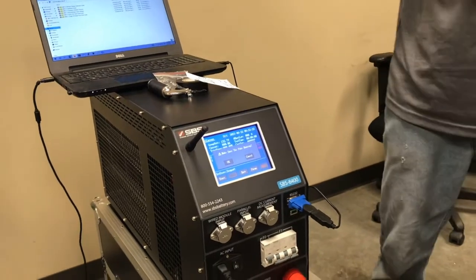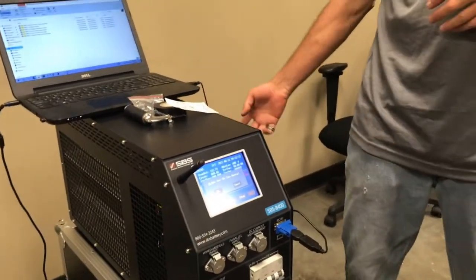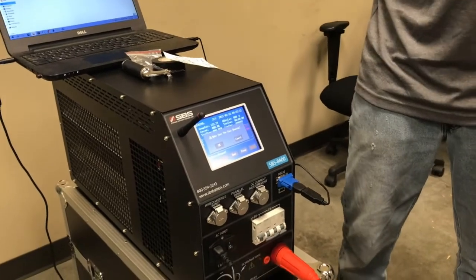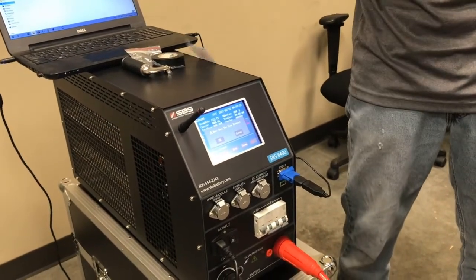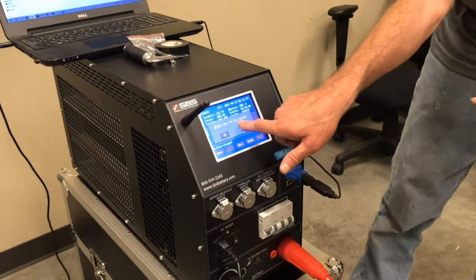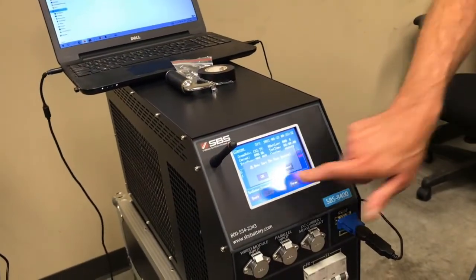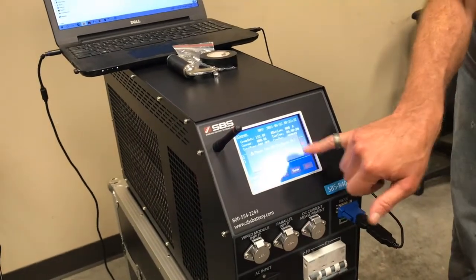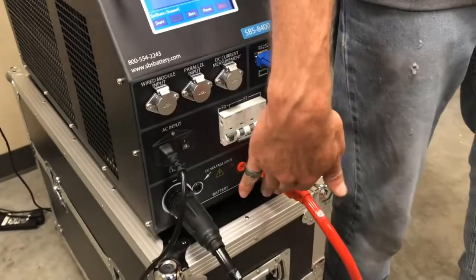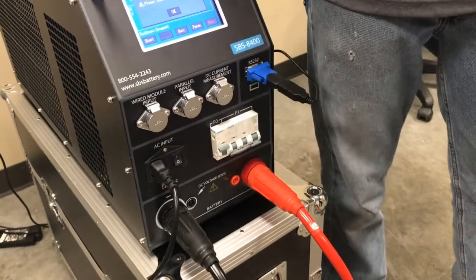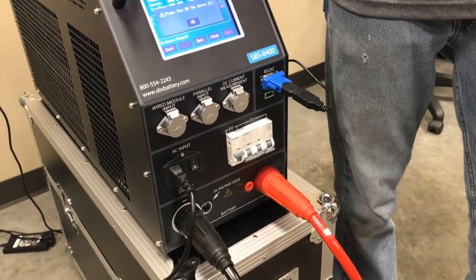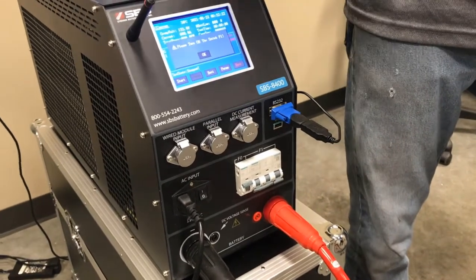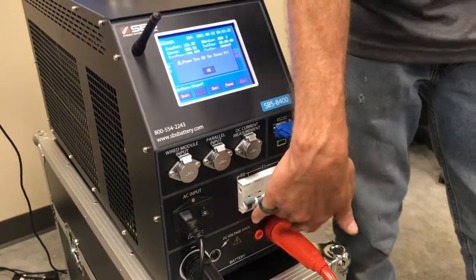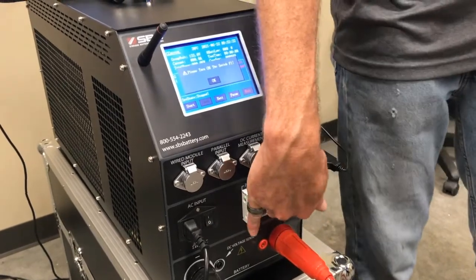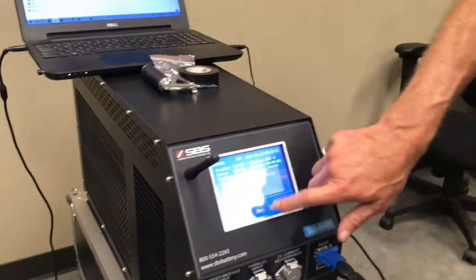I'm gonna press the start button. You're gonna hear the fans on the 8400 turn on to start airflow for cooling the load bank before the load actually gets applied. I get an acknowledgement to make sure that the fans are running. I hit OK. It's going to tell me to turn on the F1 switch. As soon as I turn this switch on, the load bank is going to start gating the IGBTs inside. It's going to start loading up the battery. We'll see voltage collapse. We'll see current rise. And it'll stabilize out at that 97 amps that we programmed it for. So I turn on the F1 switch. I press OK. The load bank starts.